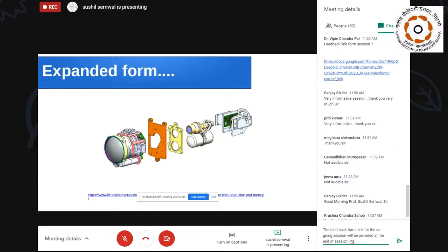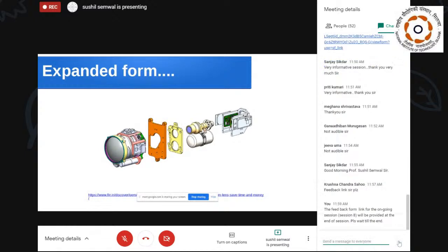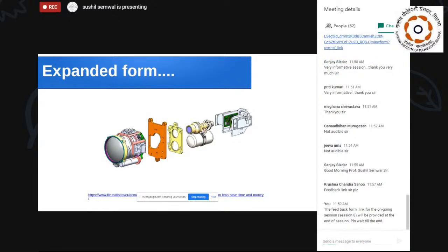For cooling it, we have a container with liquid nitrogen or helium, depending on the type of application, for cooling this Dewar in which our detector is housed. Finally, the electrical signal that we obtain from the detector through the electrical pinouts in the Dewar is further processed with the help of these electronics, and we get it in the form of an electrical signal depending on the typical application.